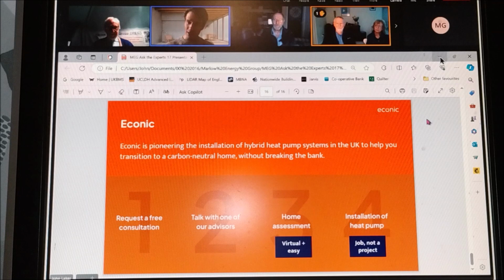So that's the idea of removing all requirement of radiator upgrades, given of course that the boiler at the moment heats your house comfortably. That's always one of the first questions we ask: if the boiler doesn't do the job today, then of course you're going to have to invest in your heating circuit overall, not just in the adjustment of the heat source. So if the boiler's all right today, you think the air source heat pump can actually be used with the same radiators?